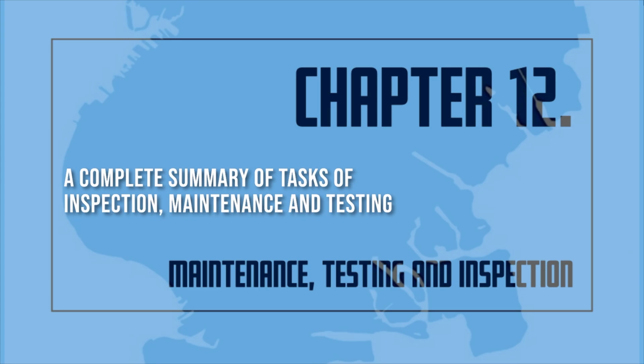Pipe and fittings shall be inspected annually from the floor level to ensure there is no mechanical damage, leakage, corrosion, misalignment, and that required supports and bracing are in place and are in good condition. Nothing shall be attached to any sprinkler system component. Pipe installed within concealed spaces, such as above suspended ceilings, is not required to be inspected. Exposed piping installed in areas that are inaccessible for safety considerations due to process operations shall be inspected during each scheduled shutdown. Pipe installed in areas that are inaccessible shall be inspected during each scheduled shutdown.